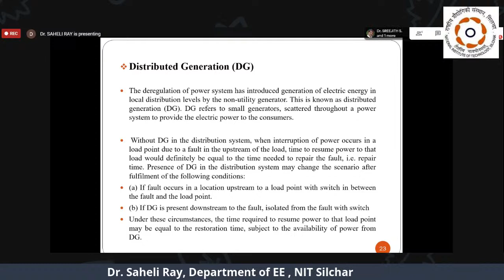Second, along with requirement A, we need a second requirement to be fulfilled. That is, a DG is present downstream of the fault location and it is isolated from the fault with a switch, right? If these two conditions are fulfilled, the time to resume power to the load point may be reduced to the switching time only, if sufficient power is available from the DG.